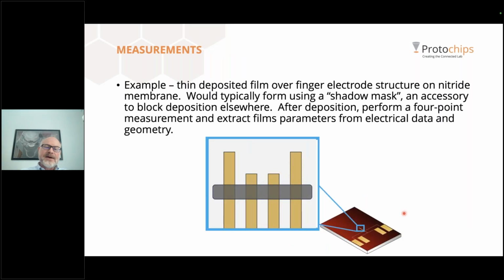And so, as an example of how they're used, consider a thin conductive film deposited over a finger electrode structure like this. So this gray is standing in for the sample. This is a material that's deposited onto that. You might form this with a shadow mask to confine its geometry, and we sell things like that as an accessory. After deposition, you can perform what's called a 4-point probe analysis. It's a 4-point measurement. You can extract film parameters and electrical data and geometry. Extracting these parameters is important. They can be used to model the films for simulation, and they help determine how they're used as a small part of a larger process. For fabrication, you track them to ensure that this is a highly manufacturable process with a high yield.